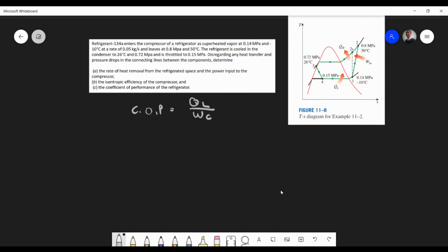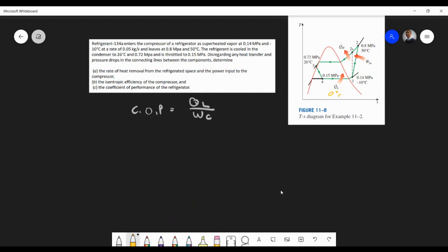This is why I want to talk about this particular pressure and temperature. If this is -10, you're probably going to find your food at 0 degrees, so that your food can actually give heat there. We can't find a situation where this is -10, otherwise heat won't actually be removed. Remember, heat moves from a high temperature to a low temperature. You could have used 5 degrees here.